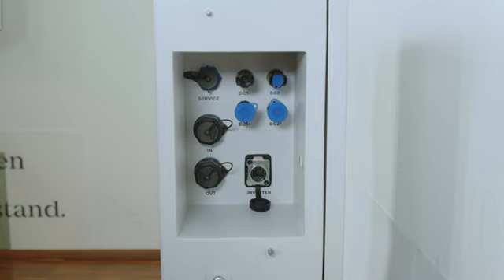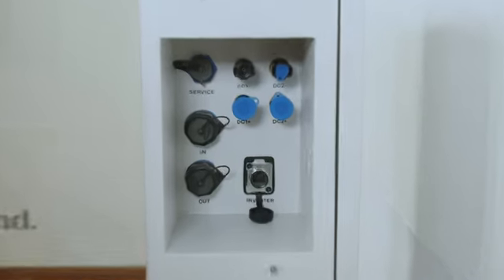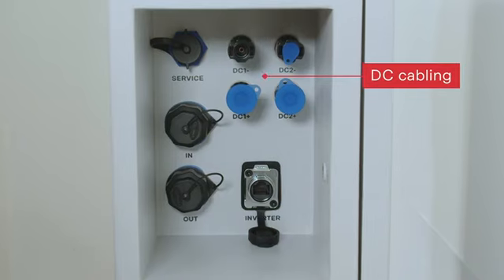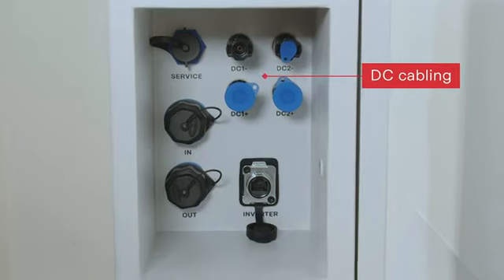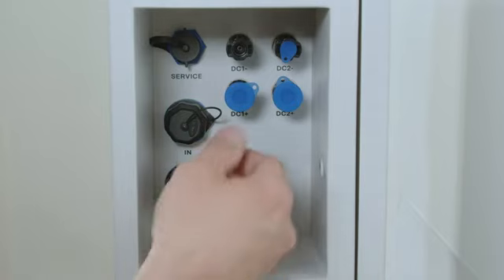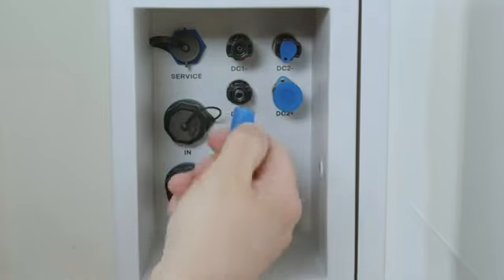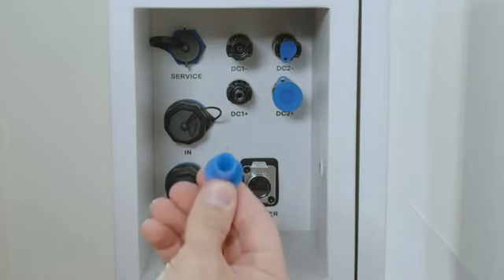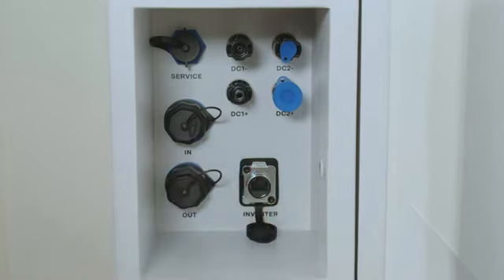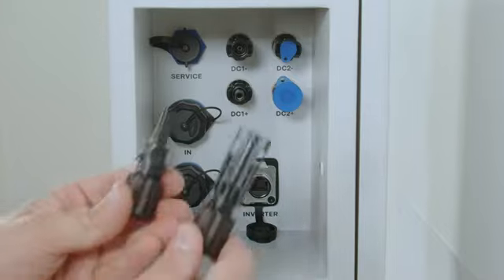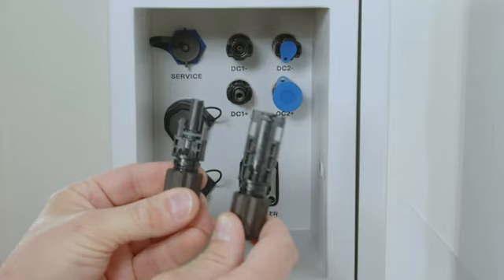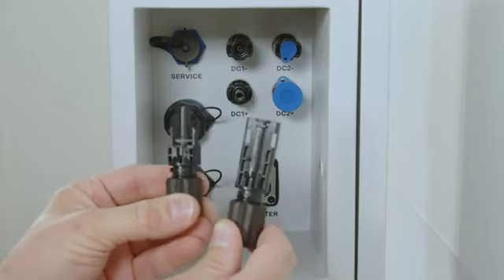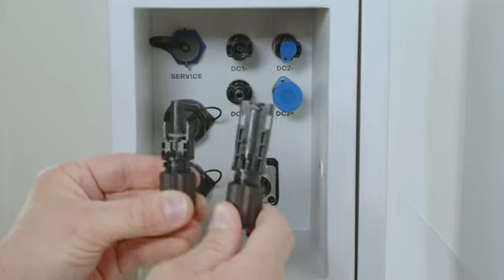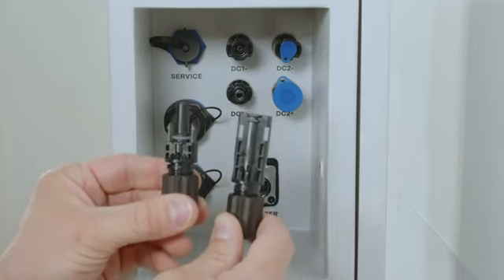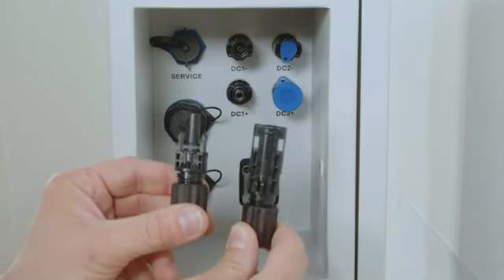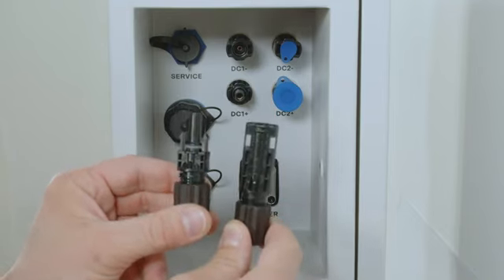After the initial installation of the battery modules, we now want to start to do our DC connection part. First of all, if ever you want to connect a hybrid inverter with the Fronius Reserva, please make sure to use the 2 DC plugs DC1 plus and DC1 minus. To connect these, please make sure to disconnect the plastic covers from the DC connection. To do so, please only use the ex-factory tools, the Amphenol DC connection parts, to do the DC connection on the battery. Please make sure to not use other DC connectors like MC4 or Stäubli to make sure to have the same type of DC connectors on the Fronius Reserva battery.